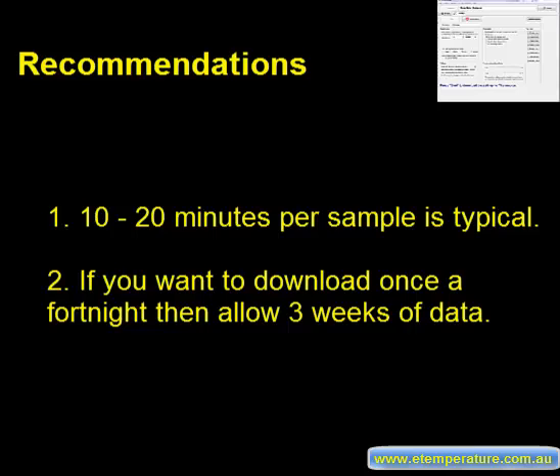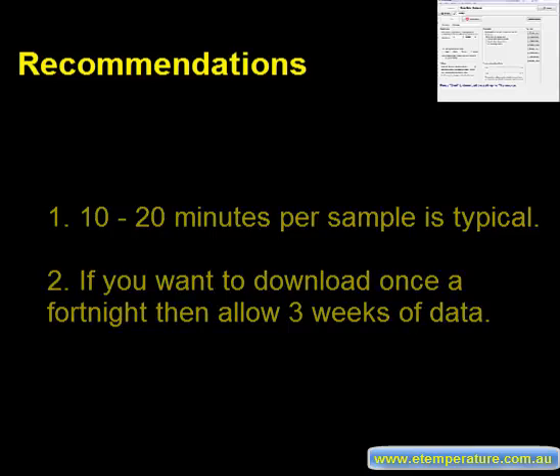If however you only want to download the results once a fortnight then we recommend to slow it down to 15 minutes. This gives you 3 weeks of data and if you are sick or away for a week over Christmas for example you won't be losing any data. With the TCS a sample rate of 10 minutes gives you a month's data.